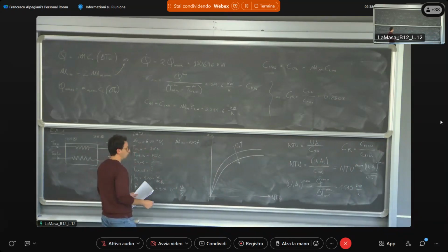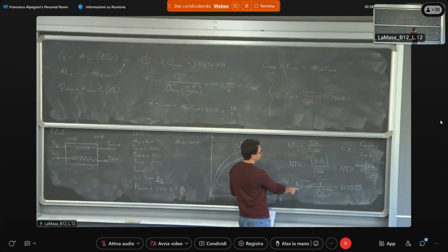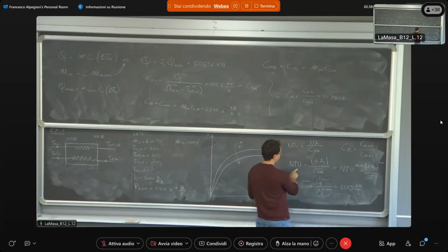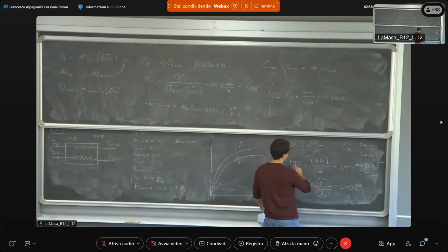Now, you have evaluated UA, and you can so evaluate the NTU, which remains equal between nominal condition and off design condition.